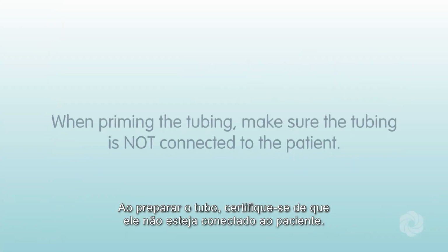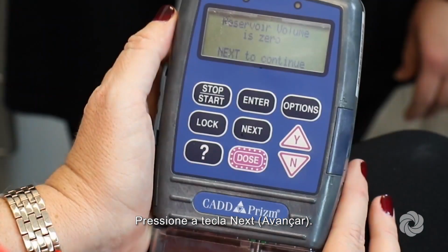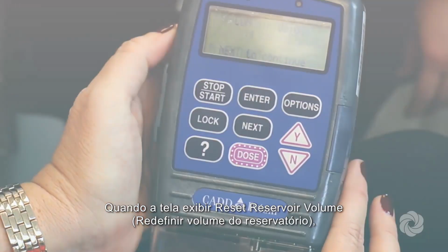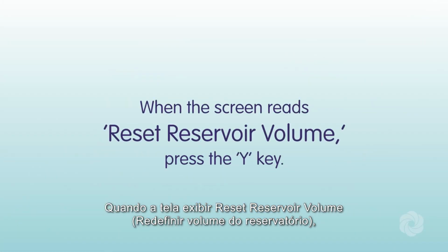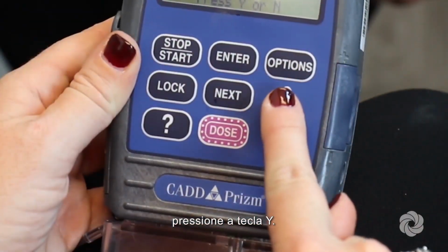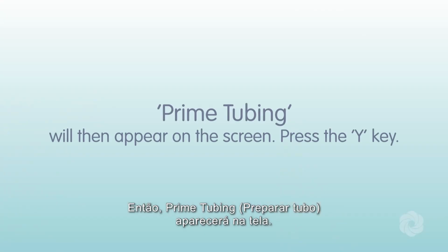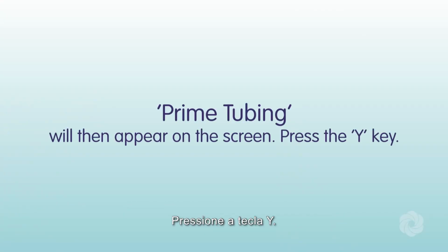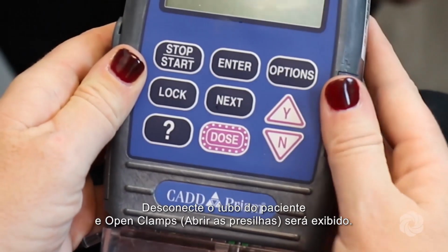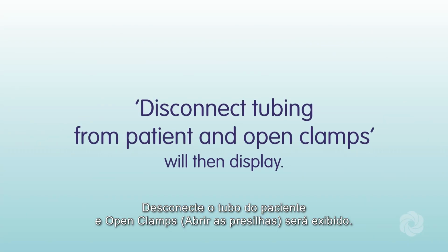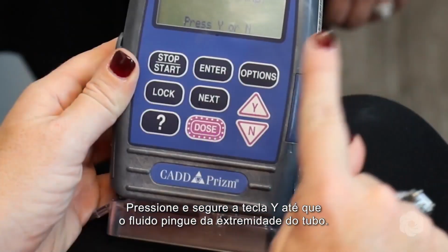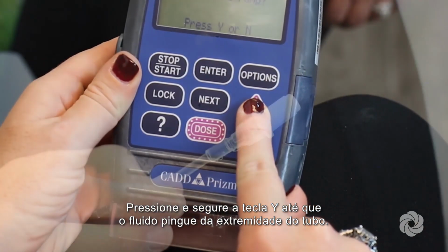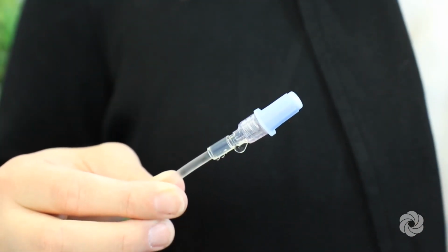When priming the tubing, make sure the tubing is not connected to the patient. Press the next key. When the screen reads Reset Reservoir Volume, press the Y key. Prime tubing will then appear on the screen. Press the Y key. Disconnect tubing from patient and open clamps will then display. Press and hold the Y key until fluid drips from the end of the tubing.